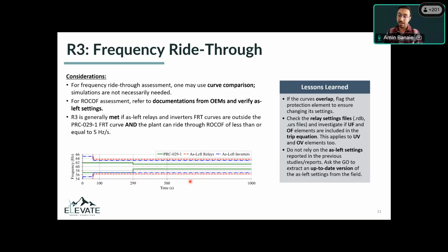And make sure to ask the generator owner to give you the most recent as-left settings of the plant, and do not rely on previous reports like PRC-24 or PRC-19 reports. Also, for the ride-through part, since this functionality is not typically implemented in PSSE, PSLF, and even some PSCAD models, we don't run simulation for this, and we rely on the documentation from the OEMs to see if that plant is meeting the ride-through requirement of PRC-29.